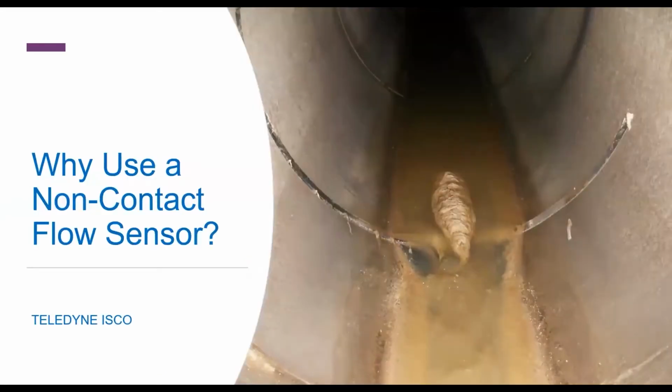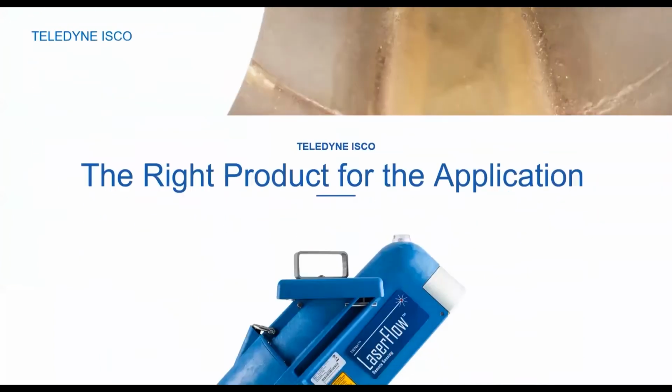Okay, so why do we use a non-contact flow sensor? Obvious reasons, and this is one of them. It gets covered. I don't care who's manufacturing this sensor, it is not going to read.